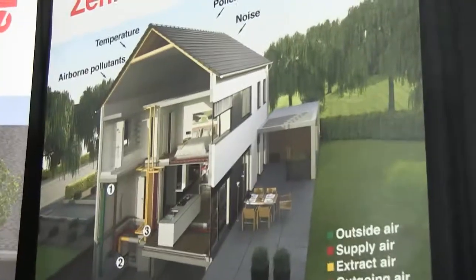Let me start with the basics. When you build a house very airtight, which is important for energy efficiency, you're air sealing the building so cold or warm outside air doesn't infiltrate. At that point you need to actively ventilate the house, since people inside need to breathe, and they're breathing out carbon dioxide and making odors that need to be exchanged. The typical way of doing that in the past has been a kitchen range hood and bathroom fans. Those don't work so well anymore once your building is very air sealed, because for all the air they move out, air needs to come back in. If you've closed off those paths, the fans just work like crazy but don't really move much air. So you need a balanced ventilation system, exhausting air out of moisture points like kitchens and bathrooms, and bringing an equal amount of fresh air back in so the building stays pressure neutral and the air is actually exchanged.